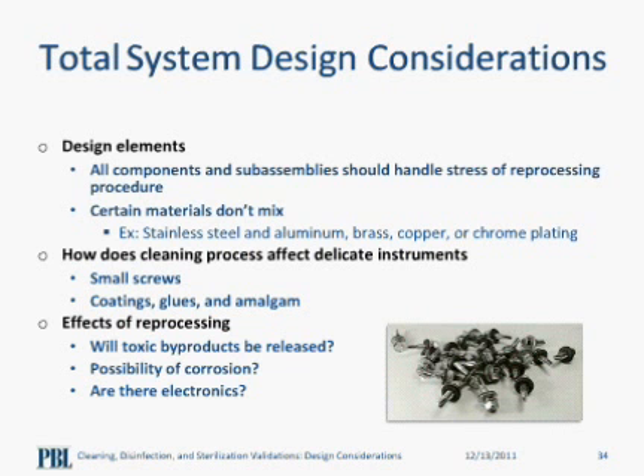What about the effect of reprocessing? Will it have an effect when the cycle is repeated over and over again? How long can a device be reprocessed and still be safe to use? Repeated processing of a device can produce toxic byproducts, and may cause corrosion, scratches, and deformities. At this time, the device has reached its limitation. Because of this, we have to determine how many cycles a device can withstand.